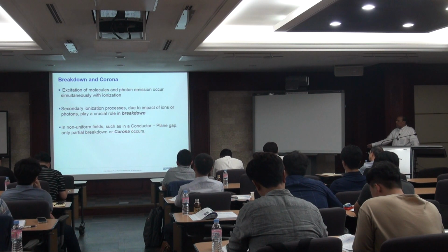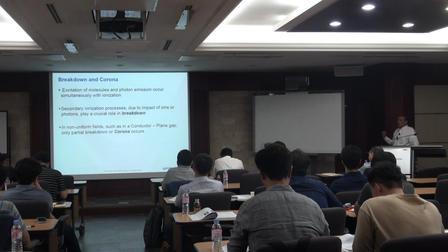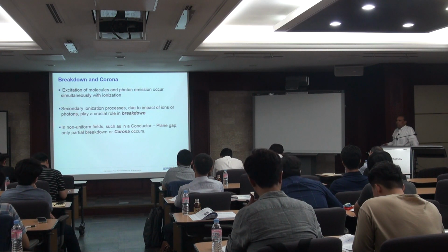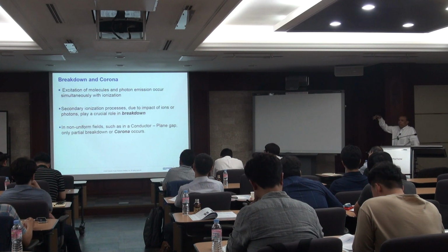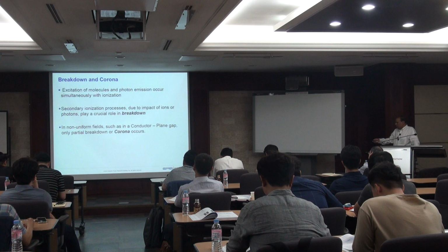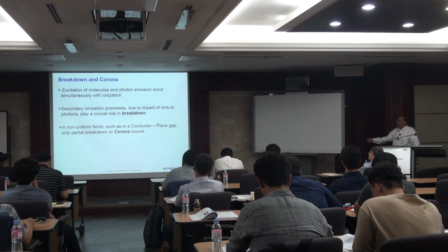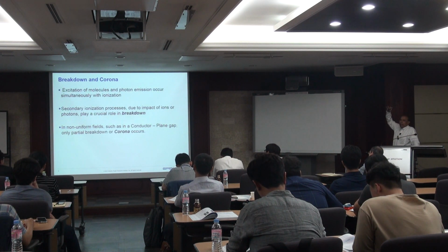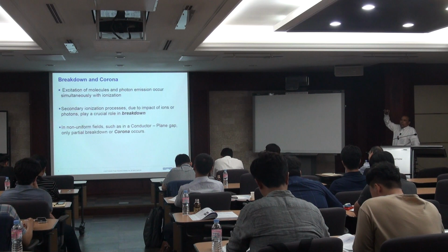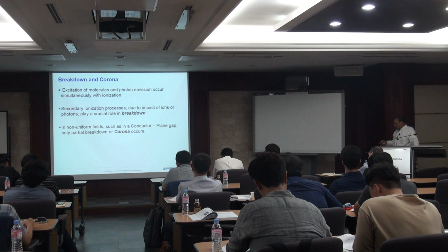So in most places when you're talking about conductors, you have a corona, not a complete gap discharge. Because if complete gap discharge occurs, it means your design is wrong. Now if you have a truck going underneath the line, you might have a complete breakdown, but that is a wrong design. So you have to design such that the height of the highest truck going underneath the line should not cause air breakdown from the conductor to the top of the truck. Okay, that's important to note.